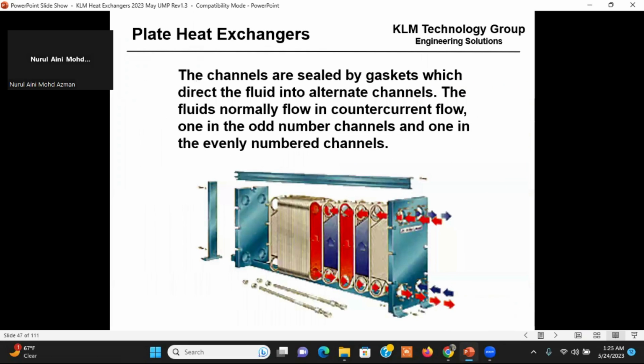These are typically used for cooling water systems. A lot of times if you have seawater, you can bring seawater in from the sea. You'll put it through a plate heat exchanger like this. And then your cooling water will be on the other side of the plates. So say, on the blue plates will be seawater. On the red plates might be cooling water. And so you will actually reject the heat out of your plant back into the ocean. And that happens at a lot of places where they actually reject heat back into the ocean. This is a common use for this plate type heat exchanger.